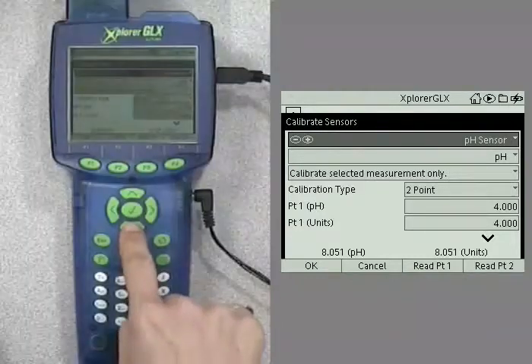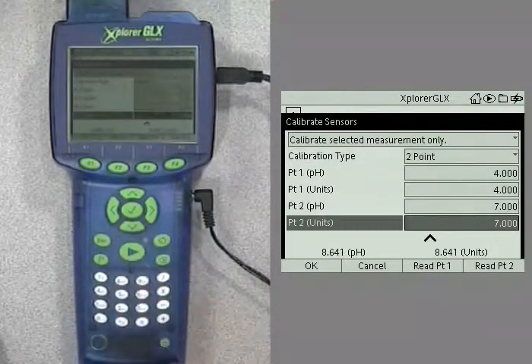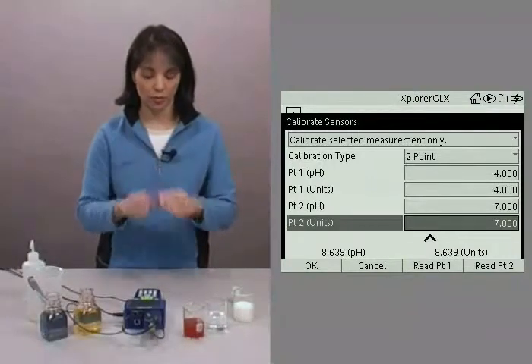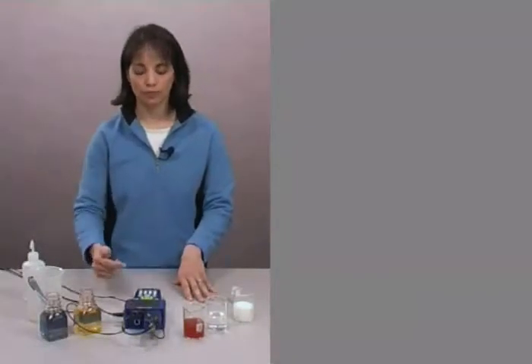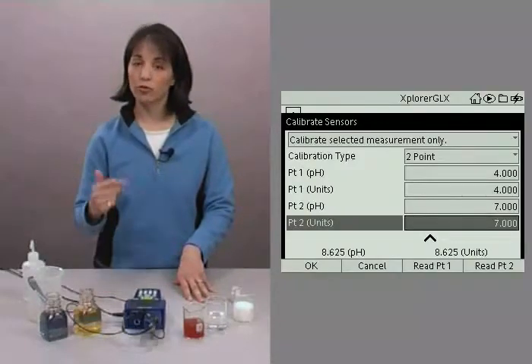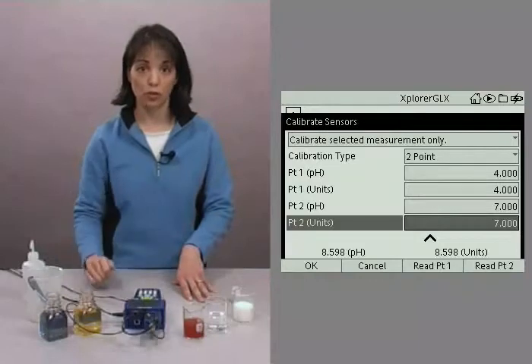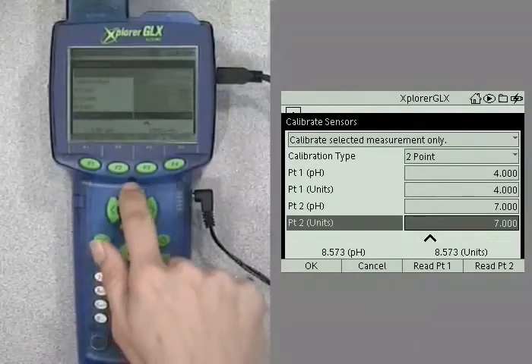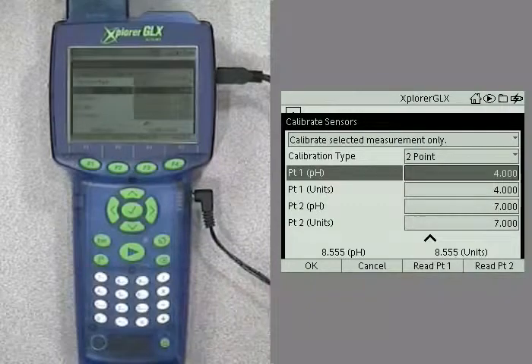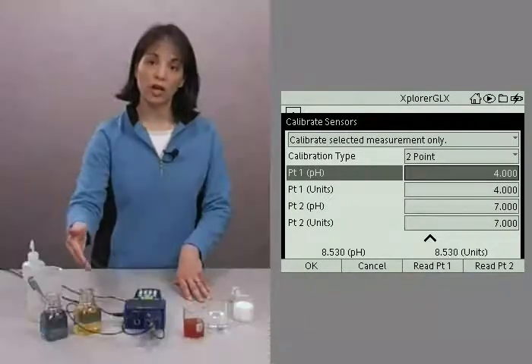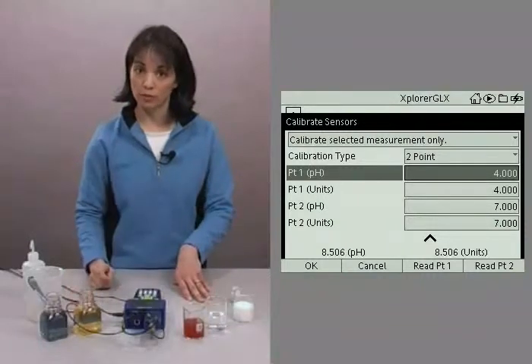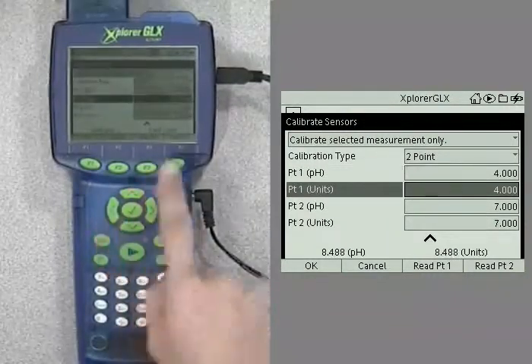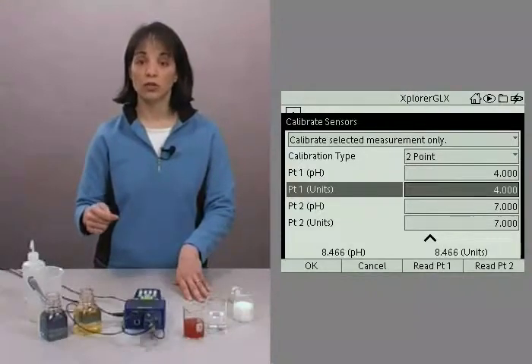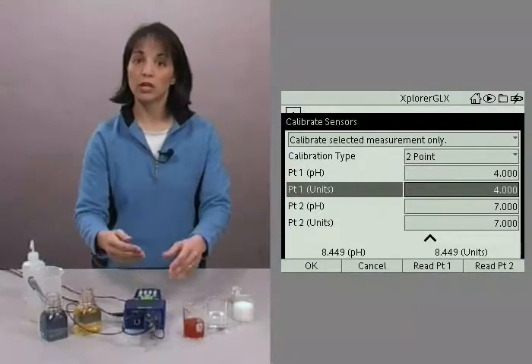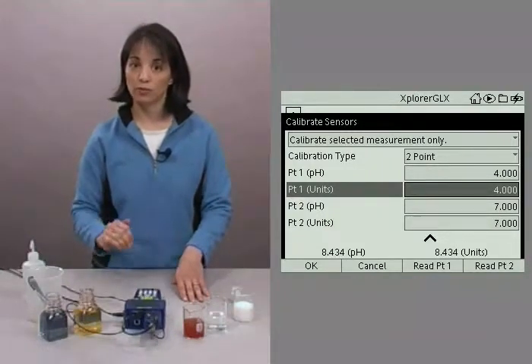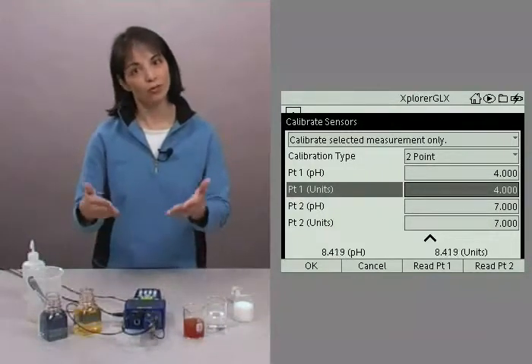First let's scroll down to the bottom of this calibration screen. And you know you're at the bottom because you see only that up arrow there. Take a look at the last 4 fields there. You see that there are 2 each related to each of the 2 points that we use for the calibration. In the first of those 2 fields, we tell the Xplorer GLX the value of the pH standard that we are using. In the second field, we tell the Xplorer GLX which raw value from the sensor it needs to associate with that standard. How do you know what raw value to put there?